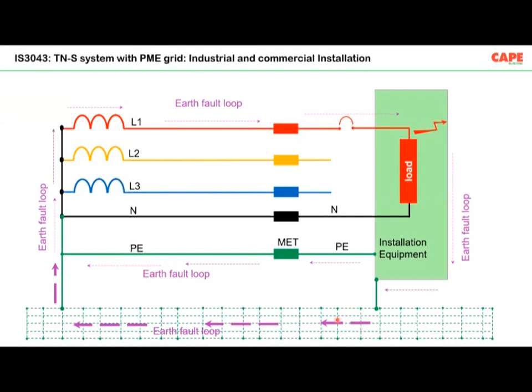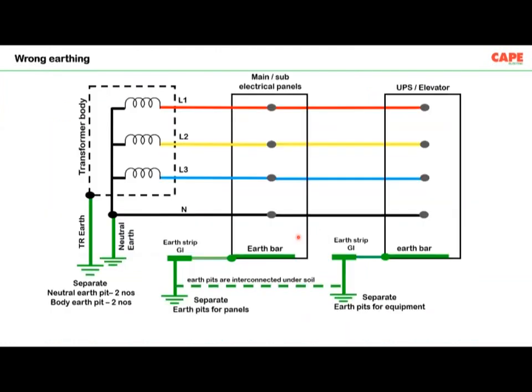And this kind of connection and earthing is very much mandatory, not only for fault loop impedance reduction, but also, as I said, to reduce the fault voltage, and to reduce the voltage of induced things such as from lightning. This is necessary to reduce the shock voltage during a high voltage fault. So all these things are very well documented, but basically this is how you are supposed to make earthing in your building, if it is an industrial or commercial building.